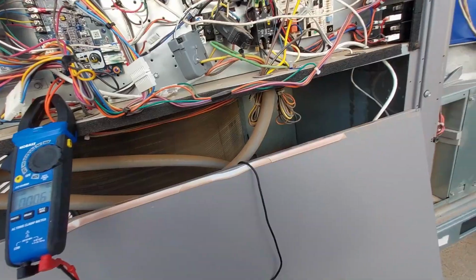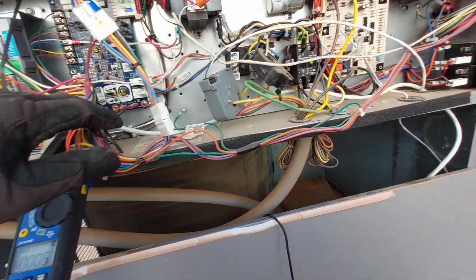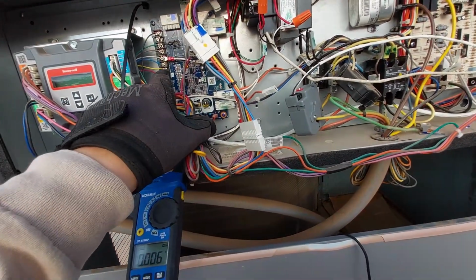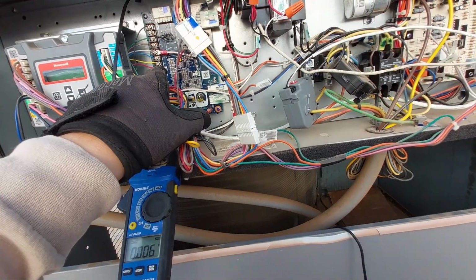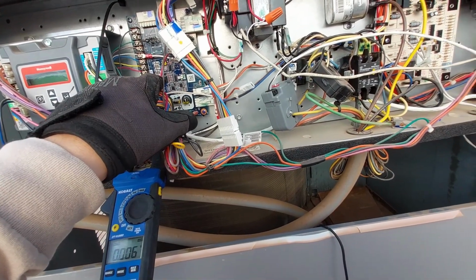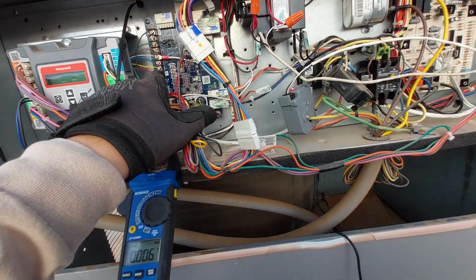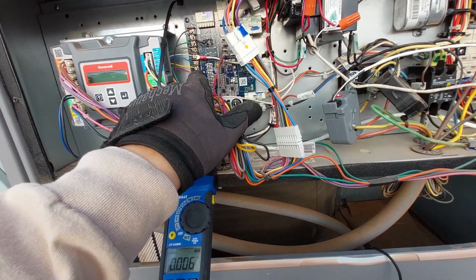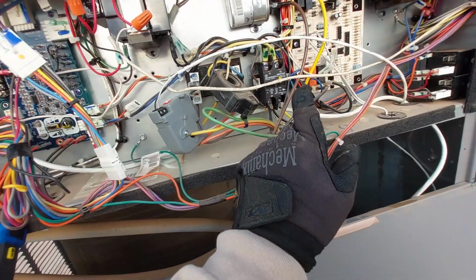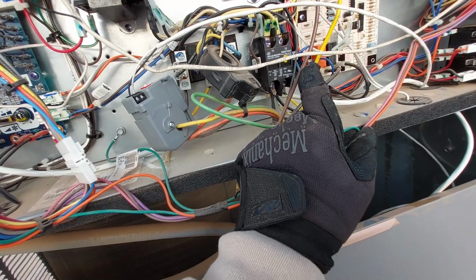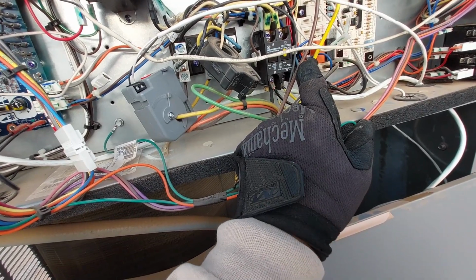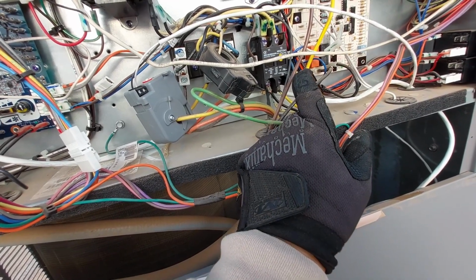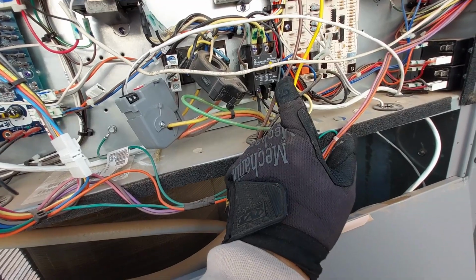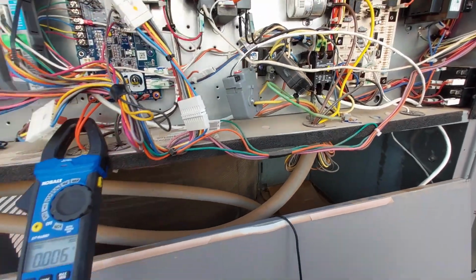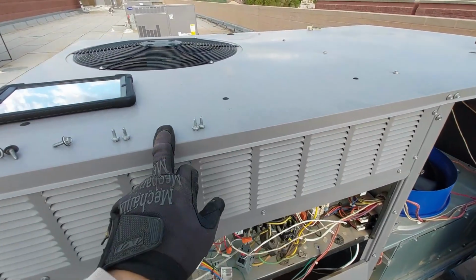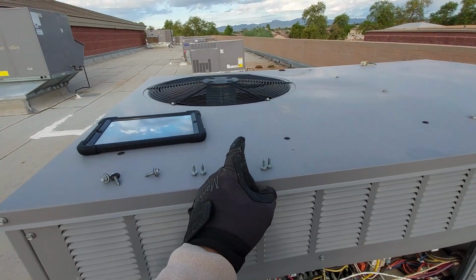So here's plan B. Since I am getting 24 volts from the thermostat, it knows that it needs cooling inside the classroom. So I'm gonna run a cable from Y1 to my 24 side of the contactor. That should engage this contactor to turn on. The thing is, I already pushed it in with the Sharpie. The only thing that came on was my compressor. The condenser fan motor did not come on.